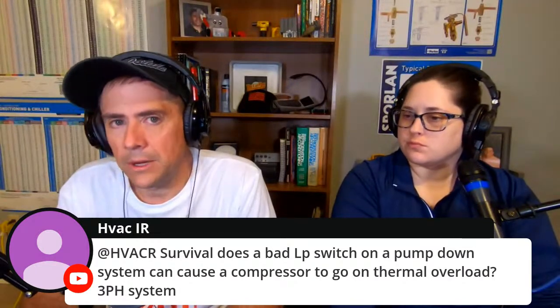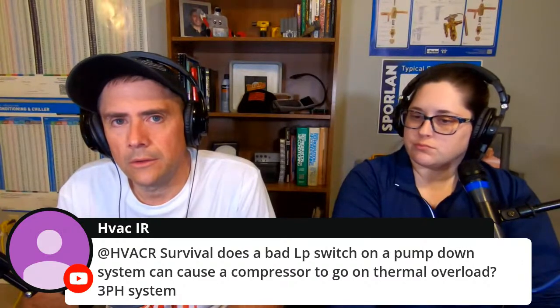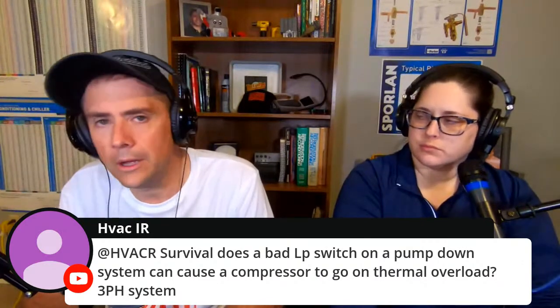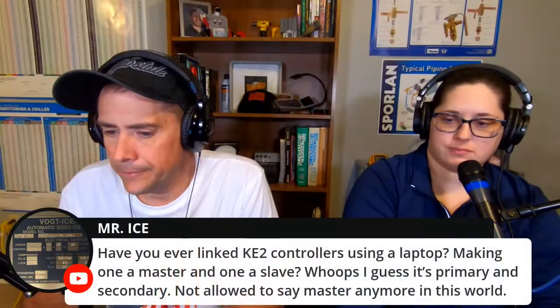If it's short cycling, possibly. If you're low on charge or something, you could pump the oil right out of the compressor. I don't know if that's the type of system involved, but it's possible. I would say check your pressure switch and see if it's in the accurate range. If not, change it, get it set up, and you may have to tweak it a little more. What else we got?